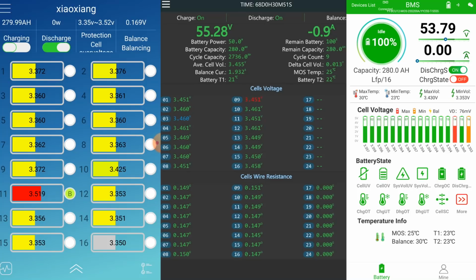So at the moment we have 2 of the 3 batteries turned off because of the overvoltage situation of one cell, and only the middle battery with the JK-BMS is still on and working. But of course it doesn't take any energy anymore at 55.2 volts, so it's shut off. It's balancing as well - 12 millivolt there, 169 on the top battery, that's a lot, and 76 in the bottom where the Heltec BMS is connected.